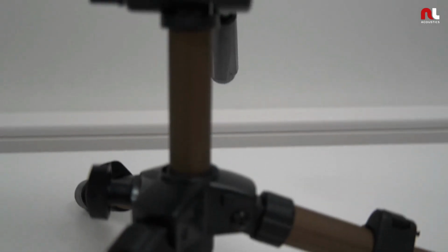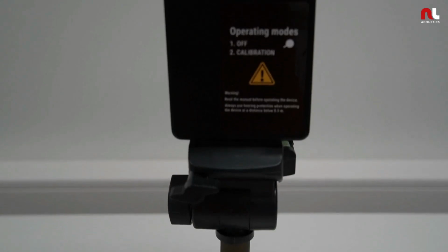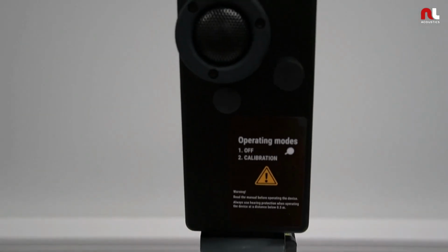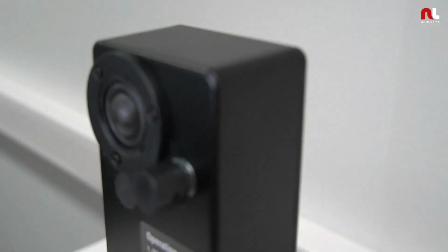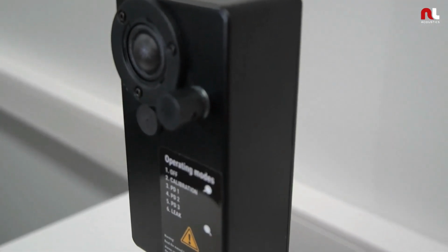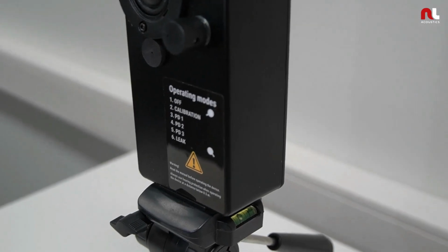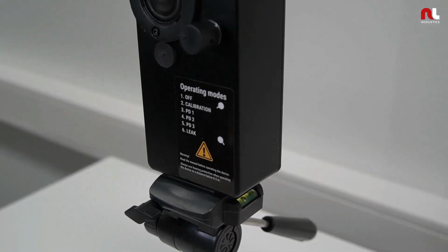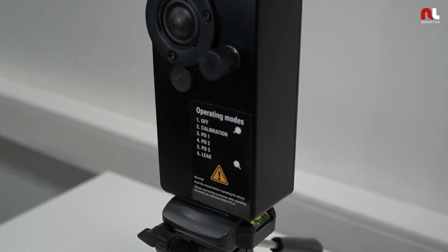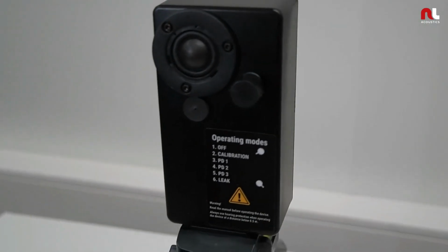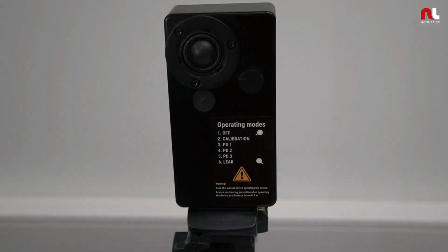The NL Sonic Tester Single is designed solely for testing purposes, as it produces a sound signal for checking if the acoustic camera's microphones function correctly. The NL Sonic Tester Multi also includes other operating modes which simulate leak and partial discharge sounds. These can be used for demonstrative purposes with the NL acoustic cameras at, for example, exhibitions and demonstrations.